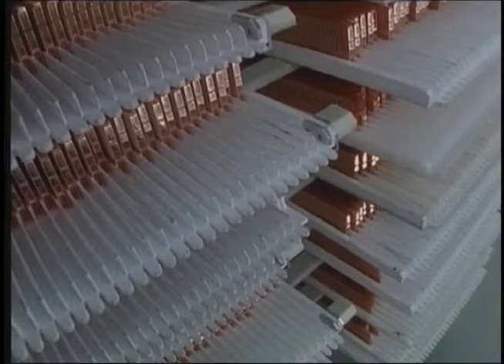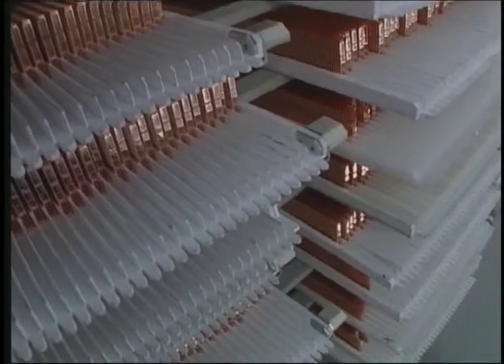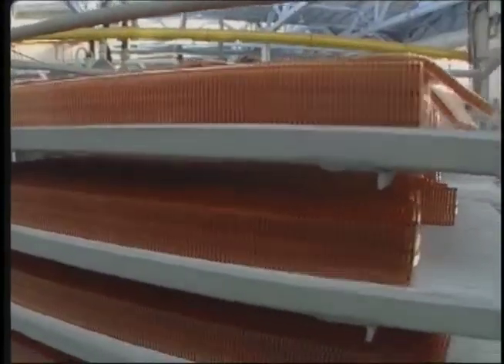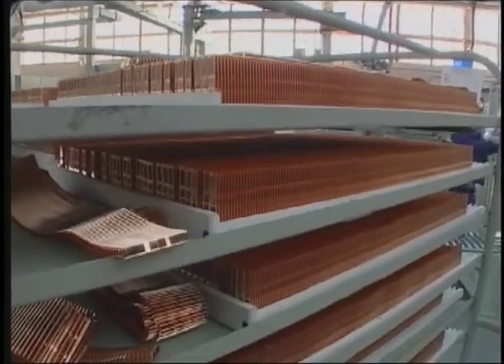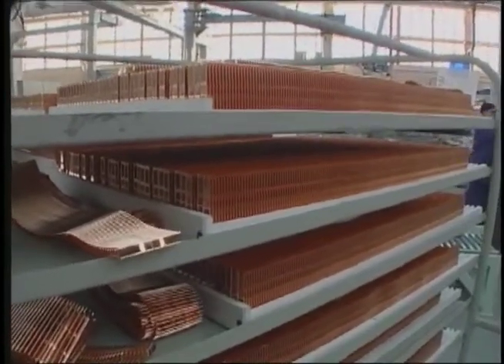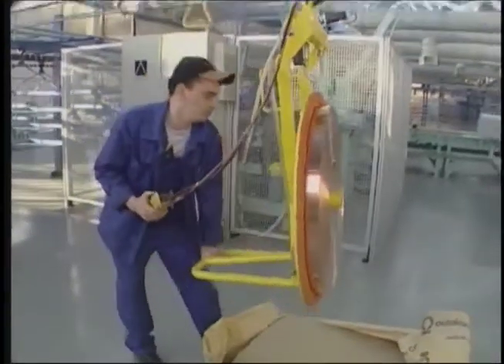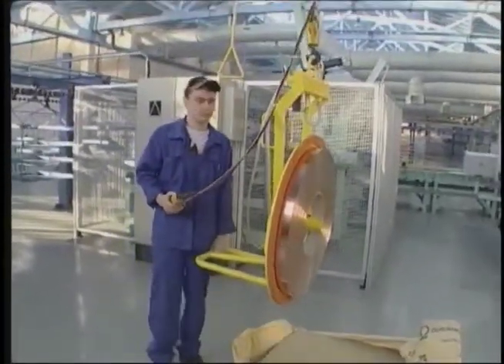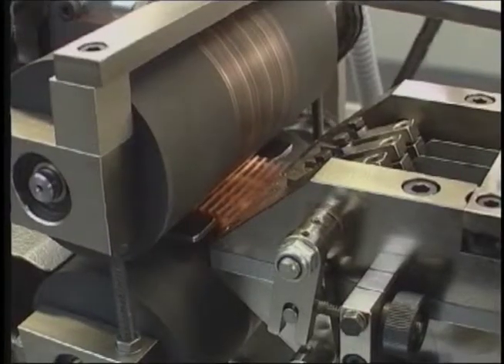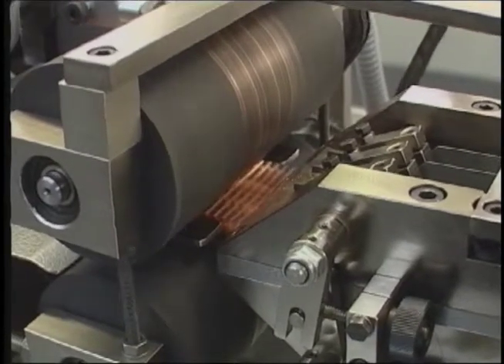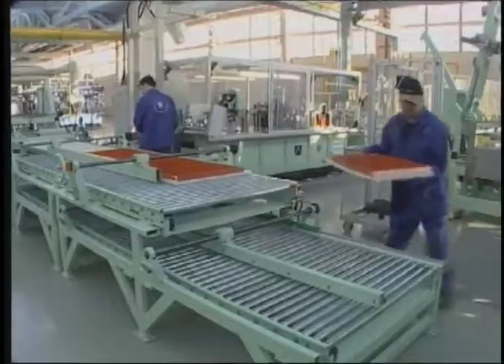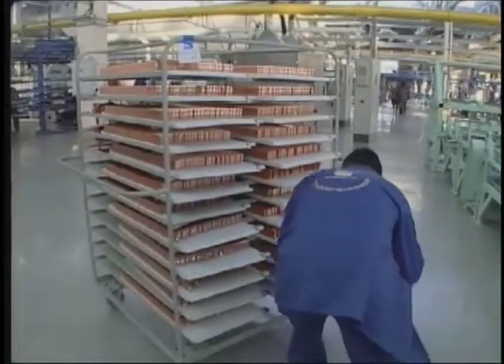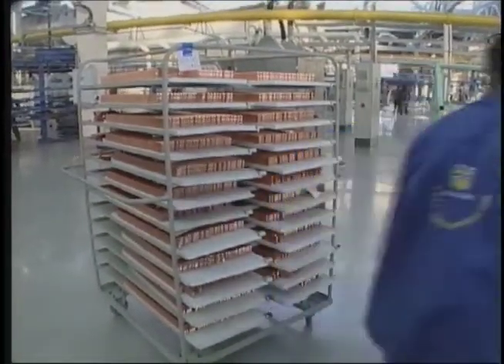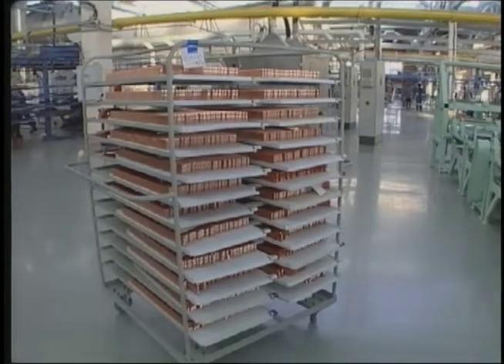Copper fins are essential to the operation of advanced heat exchangers. Their high thermal conductivity and great strength allow for the fabrication of much thinner fins than aluminum. A corrugated fin machine converts copper strip into fins. A variety of fin designs can be fabricated, depending on the application. The fins are cut to length and collected into trays. Trays of fins are stacked on a cart for transfer to the assembly areas of the plant.